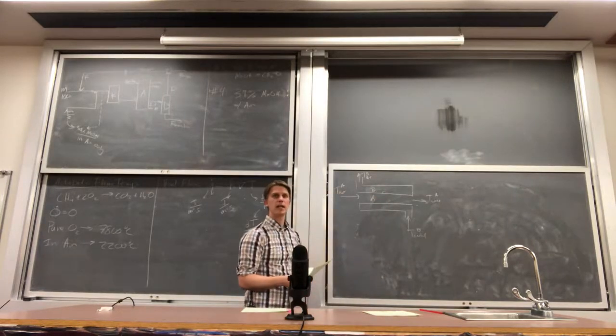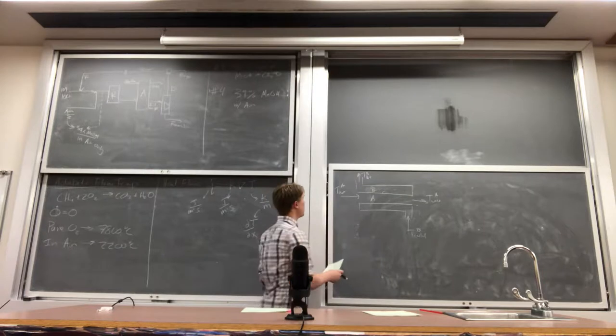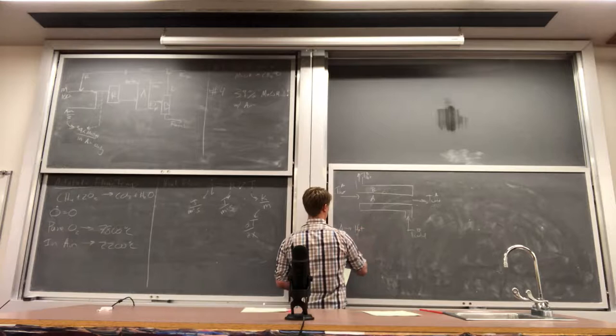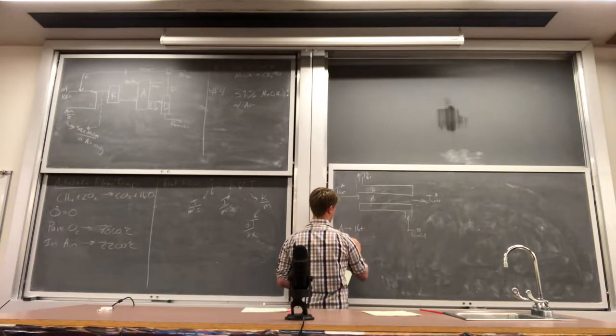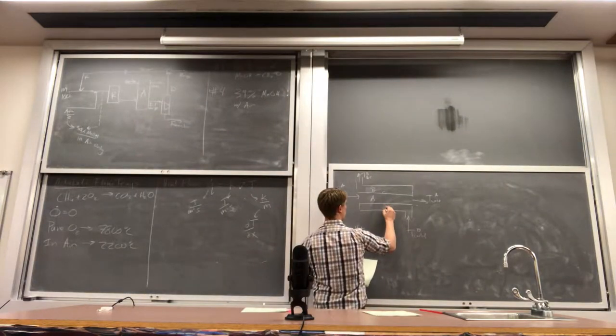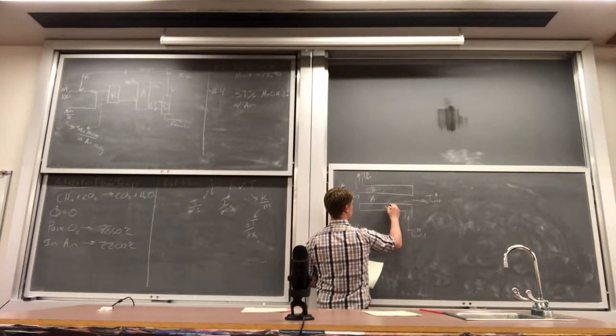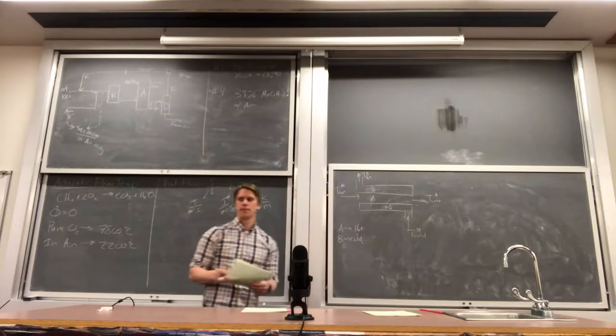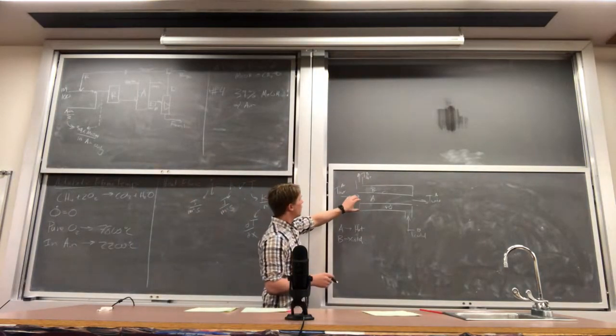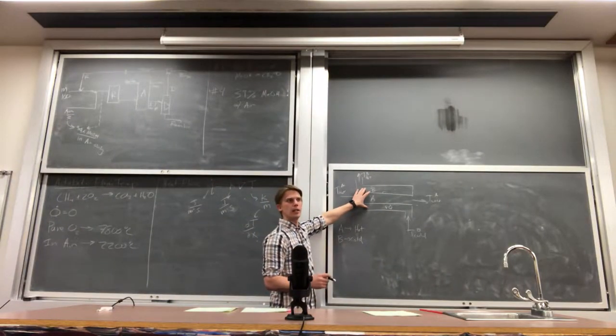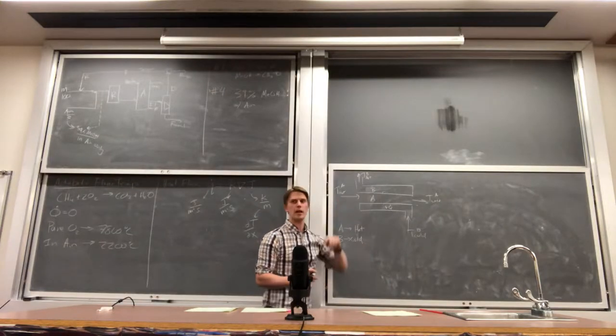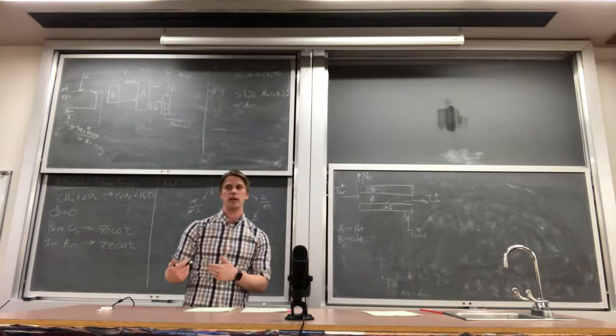Typically, this is how we'd want to design a heat exchanger. So, in this case here, A is the hot side, and C is the cold side. So, the energy in this process is going to be going like so. Now, the reason why we would design a heat exchanger like this, as opposed to the other way around, if we put the hot fluid on the outside, it would be radiating some of its energy to the surroundings, whereas if we put the hot fluid on the inside, the only place it can lose energy is to the fluid that we want to heat up.